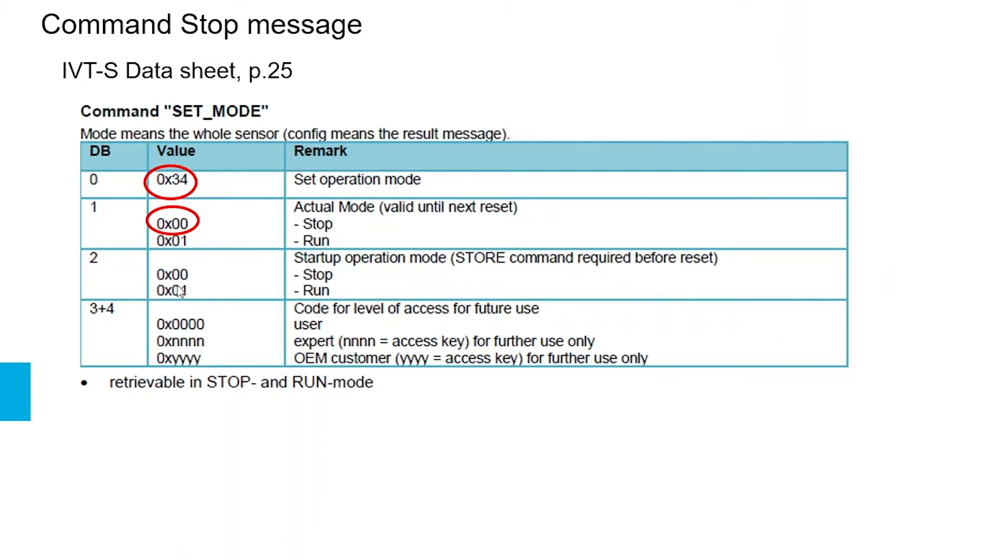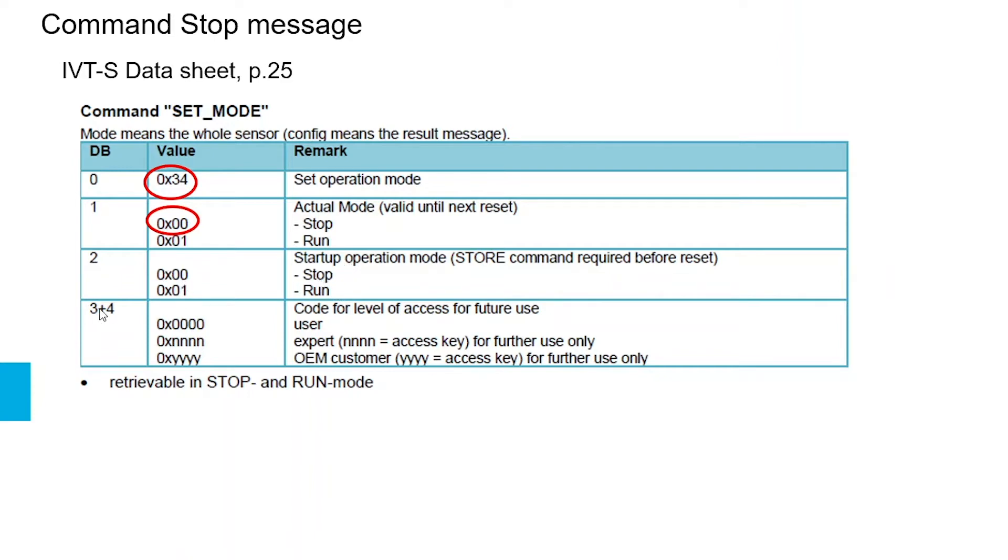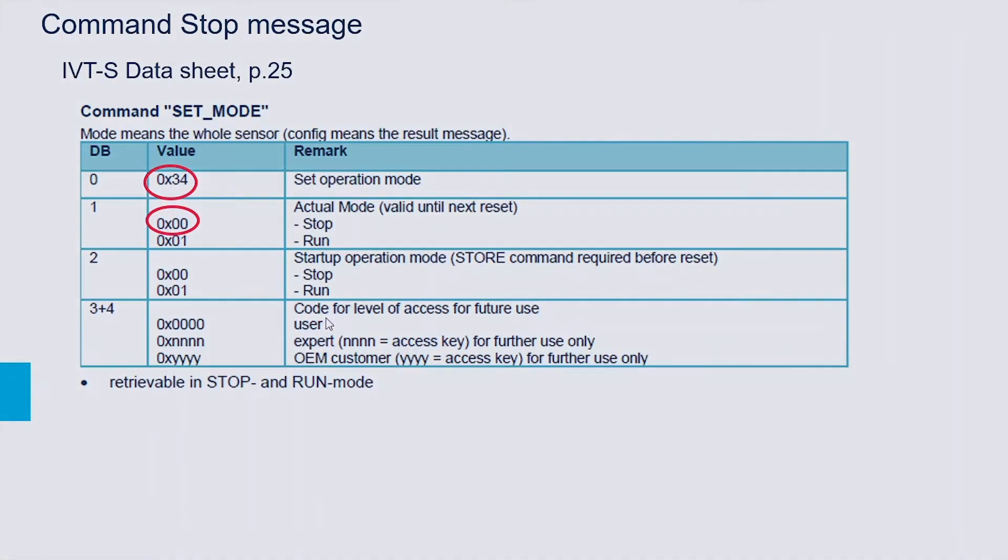Optionally we can also set the data byte 2, which is by default configured to 01 run, if we want to configure the startup behavior after the next startup, but this is not mandatory. Data bytes 3 and 4 are for future access and don't have to be used, so we can just leave them as they are at zero.